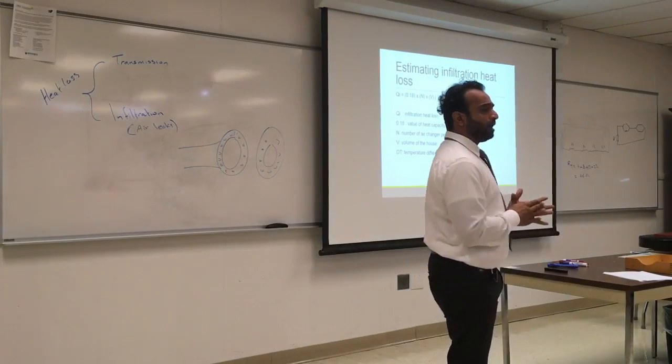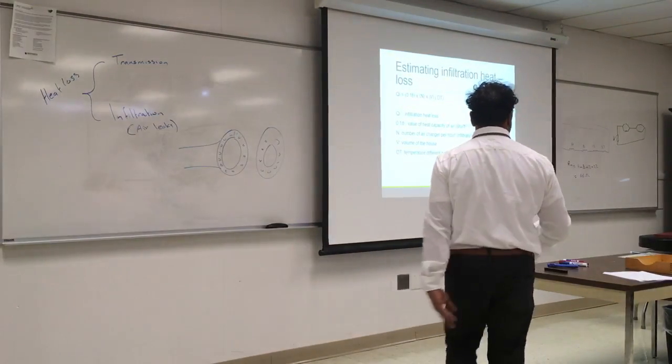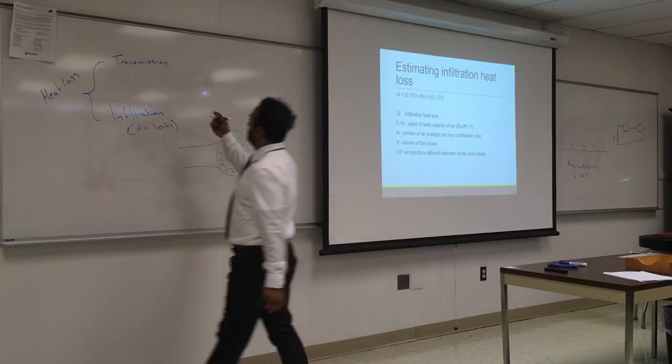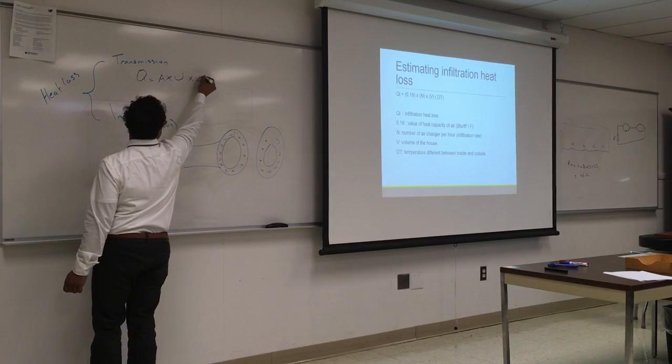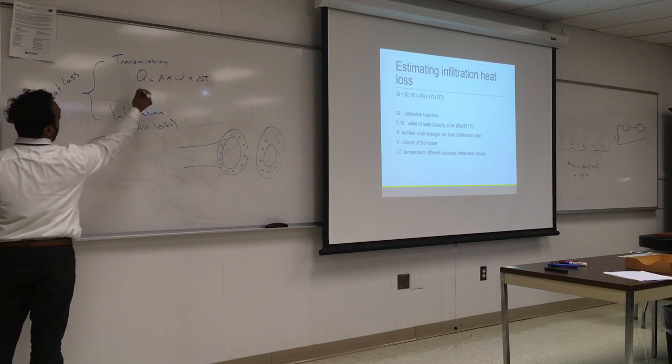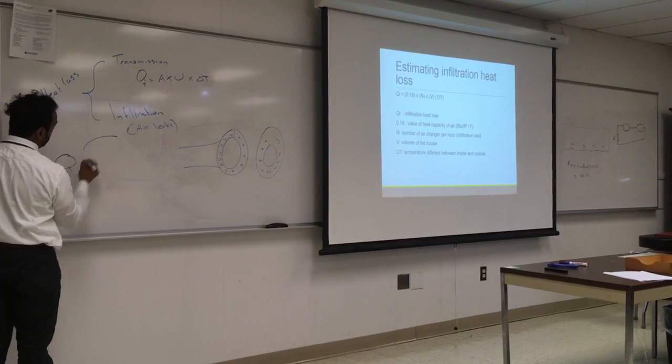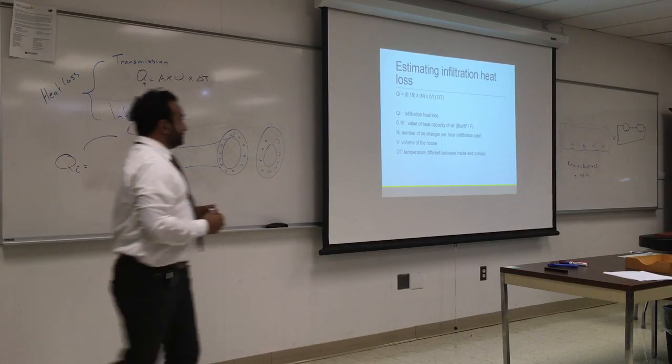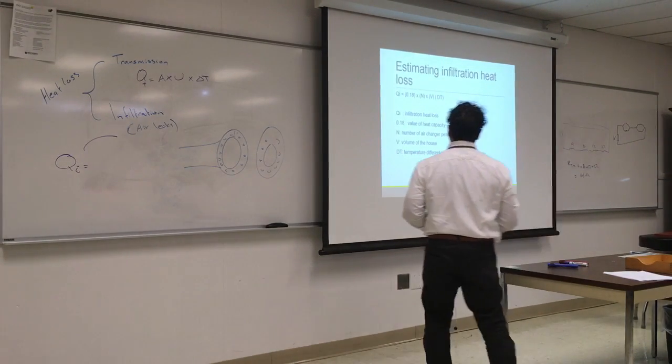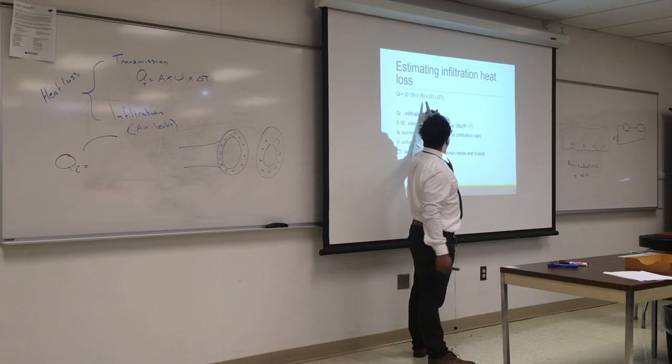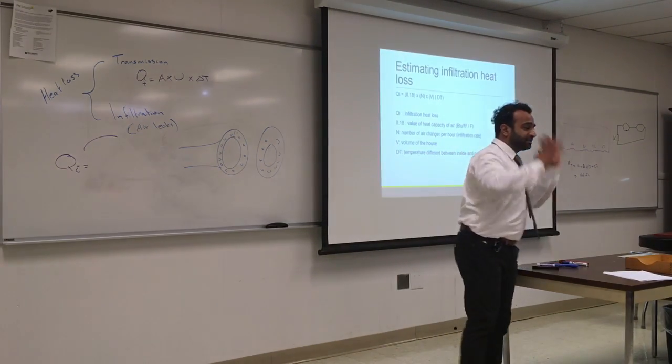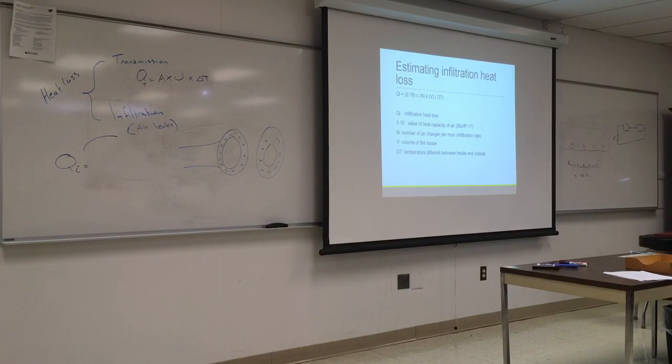I will explain this a little bit and we'll do a couple of problems on Friday. So we did a lot of equations on transmission and we said Q equals area times U times delta T. So for here we have the same thing, we're going to call this QT for transmission, this is QI for infiltration. What is delta T? We know that. V is the volume of the room. And N is the exchange rate. 0.18, it's a number that's never going to change. That's the property of air, how much the air holds heat.